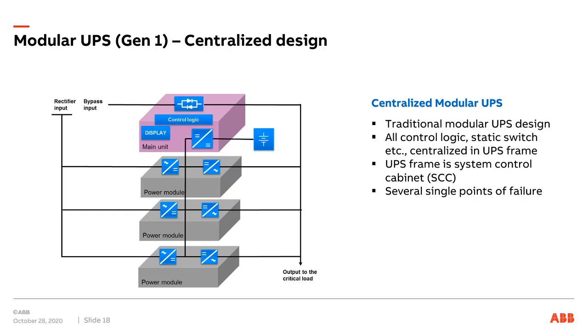If one inverter fails, it's not really a bad day, because the customer lost redundancy, but the other 2 inverters can feed the load. Or if it was 19 out of 20, 19 could feed the load even if one of them fails. The issue with this design, and this is why we learn the same stuff over and over again, is that if anything in that pink box, which here illustrates the UPS frame, if anything there fails, it doesn't help that there's redundancy on the power module side. It's still a bad day. The load is still down. So same lesson as was learned with paralleling UPSs with the system control cabinet a couple of decades before.